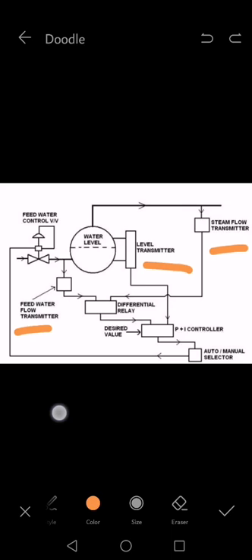In manual mode, we can keep the valve 10 percent open, 20 percent open, 30 percent open - whatever we need - looking at the steam demand and the boiler level, to see what percent the boiler level is maintaining while meeting the steam demand. So I hope your doubt about controlling the water level in the boiler is cleared.